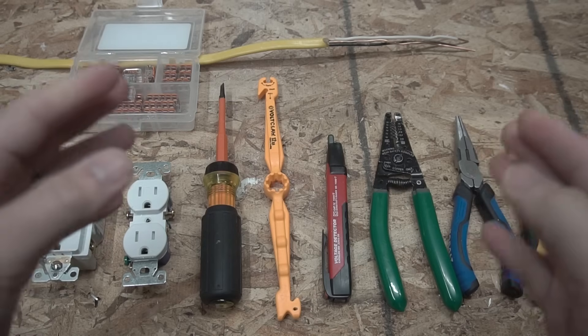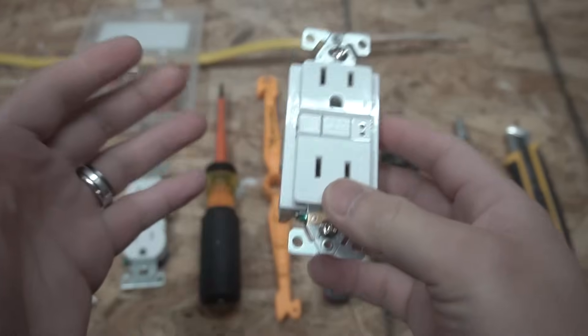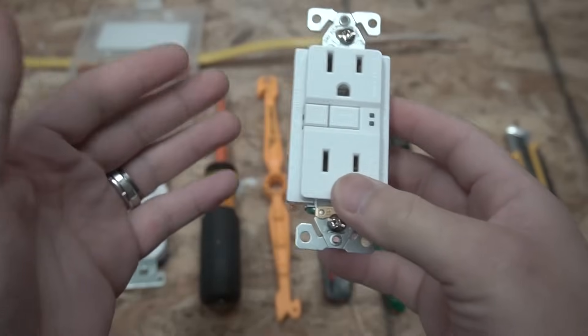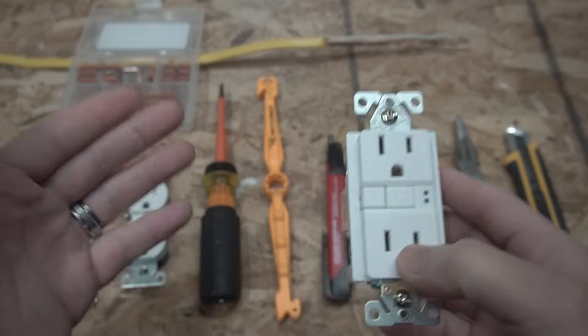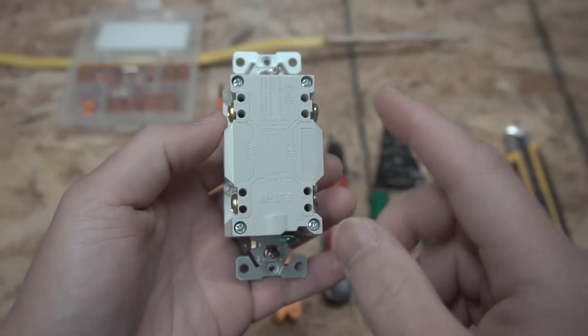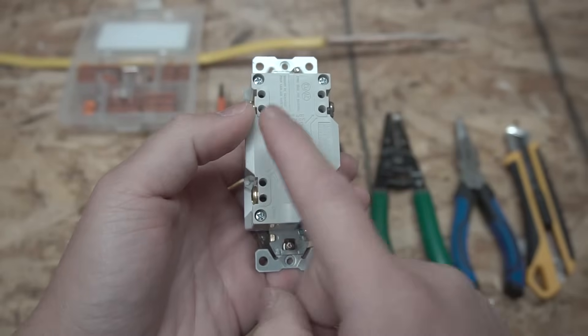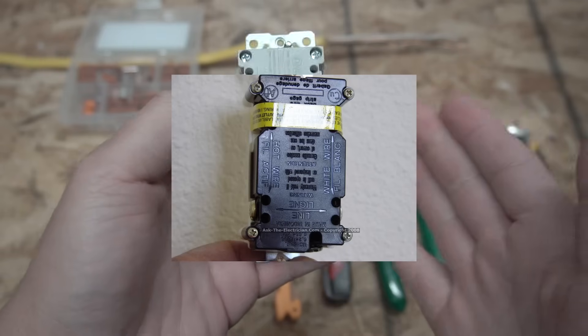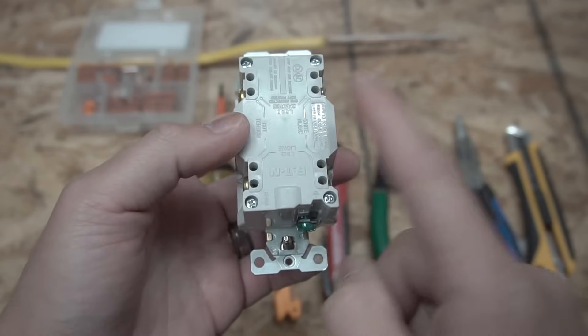So here are all the tools and materials I'll be using in today's video, including this 15-amp GFCI. Now, you can use a 20-amp GFCI as well, depending on what you need, but I'll be using and wiring it on a 12-gauge wire today because it is coming from a 20-amp circuit breaker, and that's the power source. Now, if you look in the back of this GFCI, there is no yellow tab like what you see on the older ones.